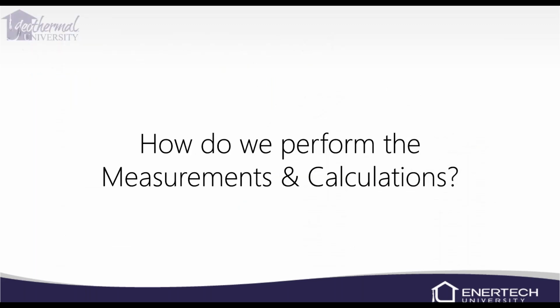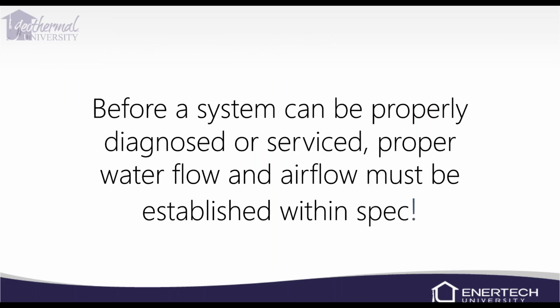So how do we perform the measurements and the calculations? Before a system can properly be diagnosed or serviced, we got to make sure we have water flow, and if it's a blower motor bearing unit, that it has airflow as well. If it's a water-to-water unit, we need to make sure that we have water flow on the load side as well. Obviously, the compressor is not going to operate properly if we don't have water flow or airflow. So it's a pretty quick, easy way to check.